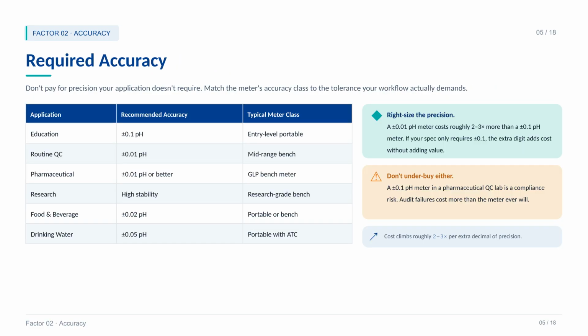Factor 2, required accuracy. Don't pay for precision your application doesn't need. Education work? Plus or minus 0.1 pH is perfectly fine. Routine QC? You want plus or minus 0.01. Pharmaceutical? 0.01 or better with full GLP features. Research grade work? High stability is the priority. Here's the thing. A higher resolution meter costs roughly 2 to 3 times more. If your spec only requires 0.1, that extra digit on the display is just wasted budget. Right-size the precision to the workflow.